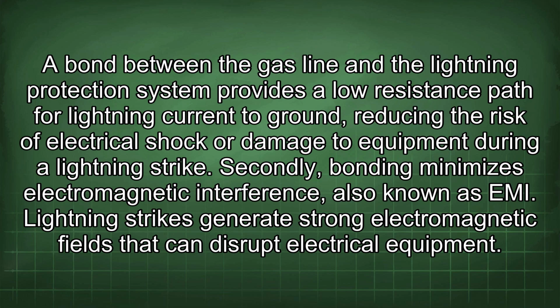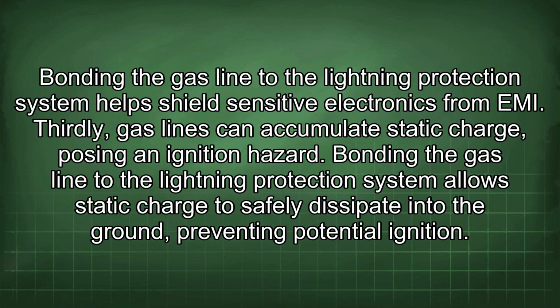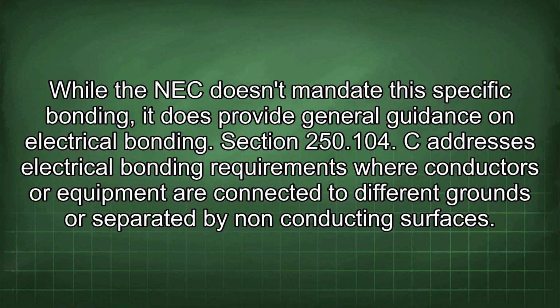Secondly, bonding minimizes electromagnetic interference, also known as EMI. Lightning strikes generate strong electromagnetic fields that can disrupt electrical equipment. Bonding the gas line to the lightning protection system helps shield sensitive electronics from EMI. Thirdly, gas lines can accumulate static charge, posing an ignition hazard. Bonding the gas line to the lightning protection system allows static charge to safely dissipate into the ground, preventing potential ignition. While the NEC doesn't mandate this specific bonding, it does provide general guidance on electrical bonding.